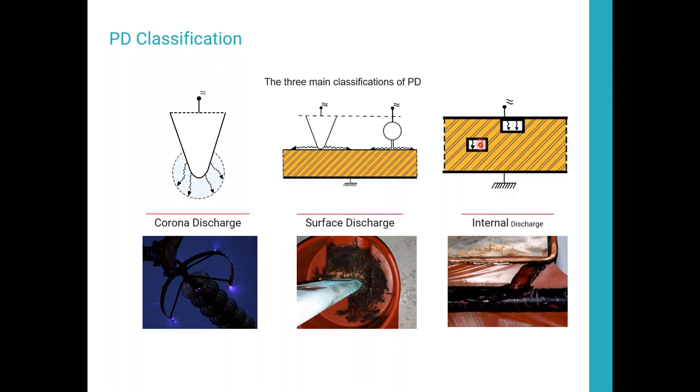Internal discharge, as the name implies, is a breakdown of the insulation inside. So you've got a solid insulator, there's a defect or void within the insulation, it has a lower voltage withstand, and there's arcing happening within the insulation. This picture here is a cast resin CT, current transformer.